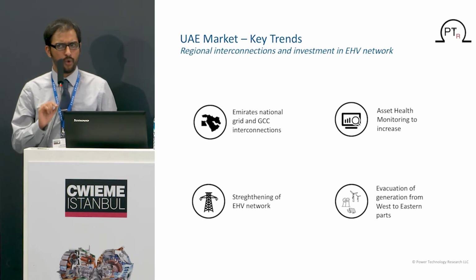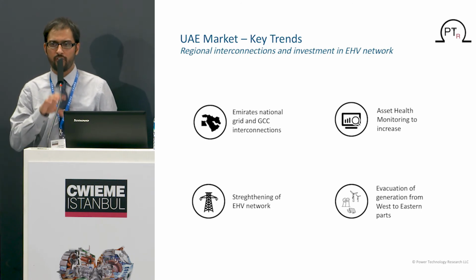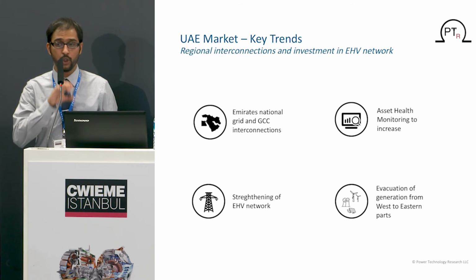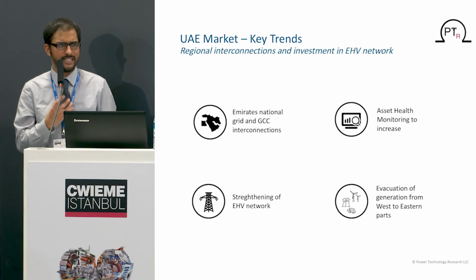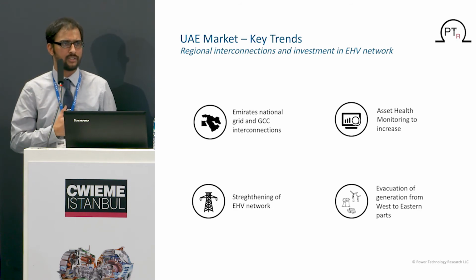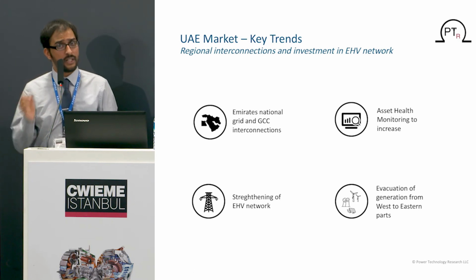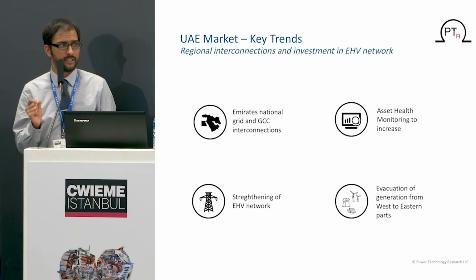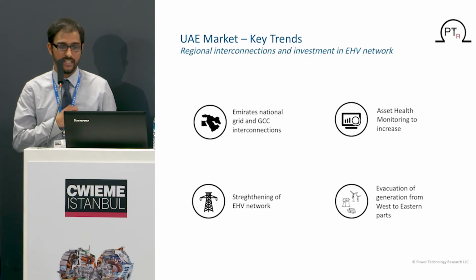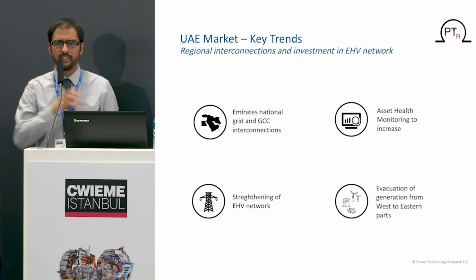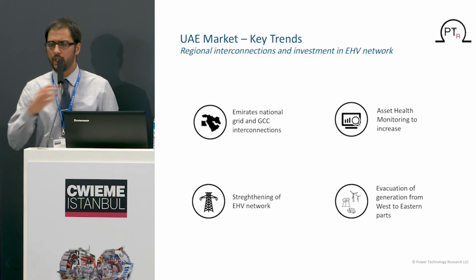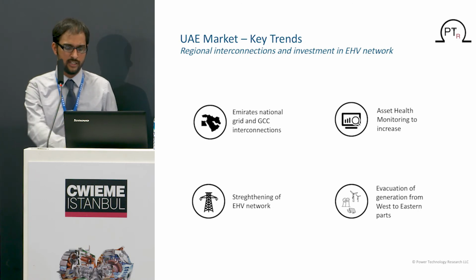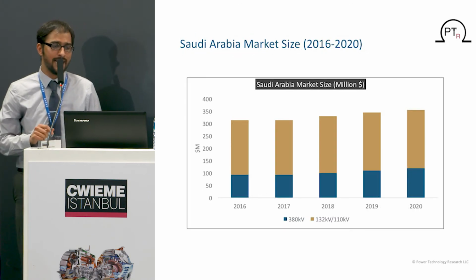The 400 kV network saw a lot of power transformer investment because it acts as a backbone for the network, which is why they're strengthening it. The 132 kV network is also getting strengthened rather than 220 kV, because of renewable generation connecting at 132 kV, needing to move power from generation points to load centers.